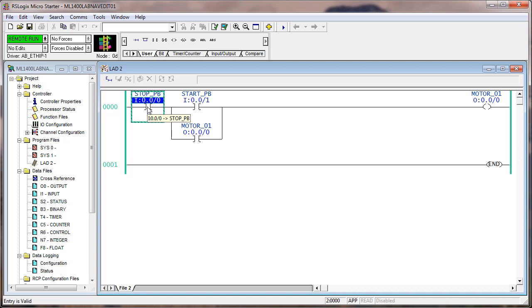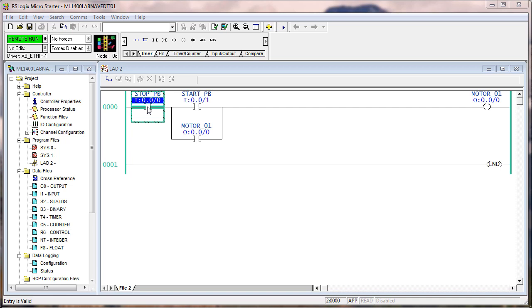So what I'm going to do is turn on switch 0, and you see now it's true. Now if you're using my simulator, I have it wired up so you can use it as maintained on, maintained off. If the switch is up and on, then the push button next to it is connected as a normally closed. So if I push that push button, watch the stop push button. See, it goes false. I'm not pushing, now I am pushing. They're enhanced inputs, so you can use maintained on, maintained off, or normally closed, normally open.